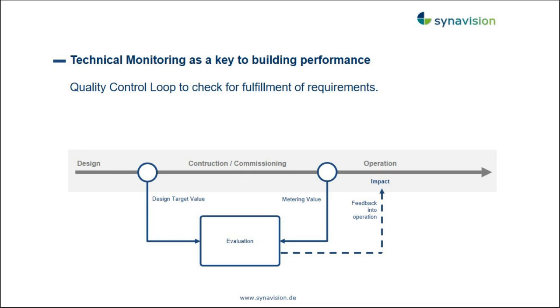So you have to have an early impact, and you have to have a precise impact. You have to tell people exactly what the problem is. If you tell them the performance of the building is not good, nobody's interested. But if you tell somebody, 'this valve is not moving correctly,' then you have somebody to address. This is the key element of technical monitoring that we are proposing.